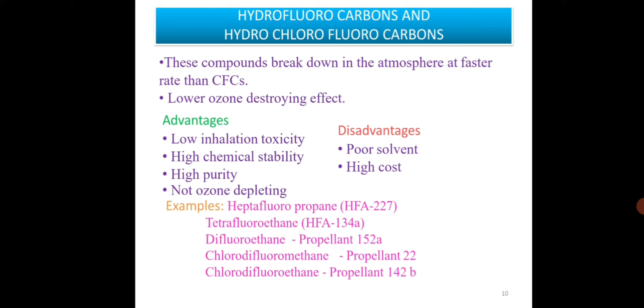Nomenclature of propellant. All propellants are designated by 3 digits: 0, 0, 0. When the first digit is 0, the propellant is designated by the last 2 digits and 0 is assumed to be the first digit. Example: propellant 011 is propellant 11. The first digit is 1 less than the number of carbon atoms in the compound. When there are only 2 digits, 0 is understood to be the first digit and indicates the methane derivative. When the first digit is 1, the propellant is an ethane derivative. When the first digit is 2, it is a propane derivative, and when the first digit is 3, it is a butane derivative. The second digit is 1 more than the number of hydrogen atoms in the compound. The last digit represents the number of fluorine atoms. The number of chlorine atoms for CFCs, chlorofluorocarbons, in the compound is found by subtracting the sum of fluorine and hydrogen atoms from the total number of atoms that can be added to saturate the carbon chain.